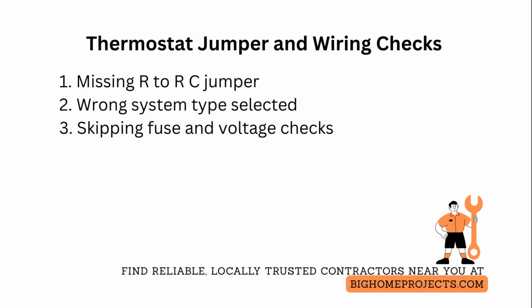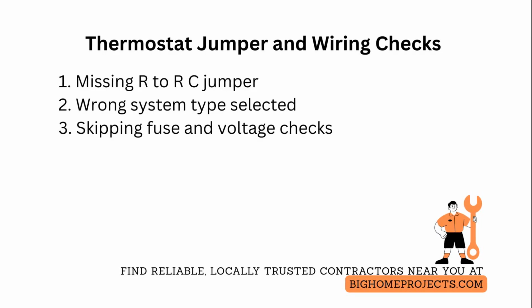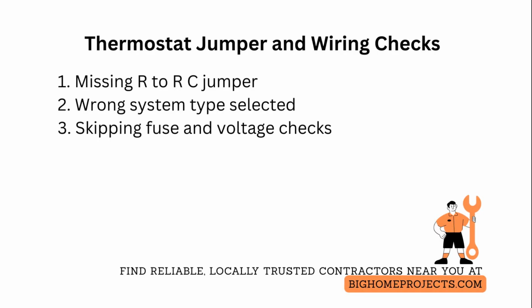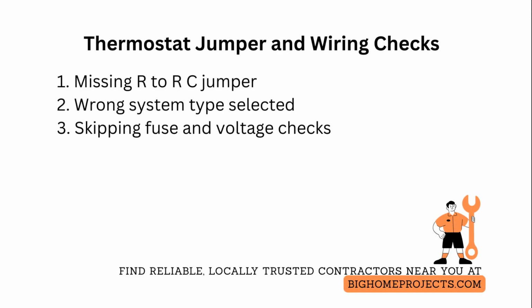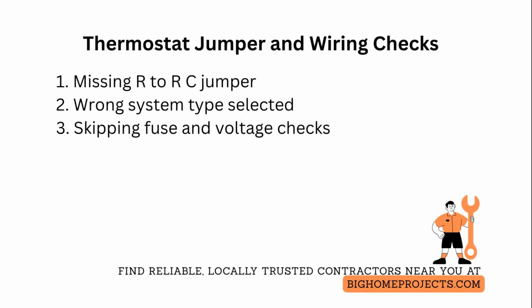One of the last repeated problems is skipping the fuse and voltage checks, leading to burned controls or no response. Fix by testing the 24-volt fuse at the control board, replacing it with the exact rating if blown, and measuring 24-volt presence at R and RC before connecting the thermostat.